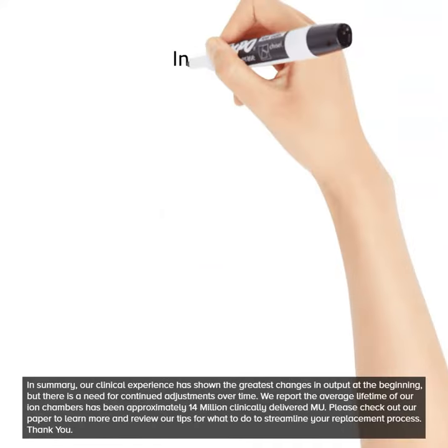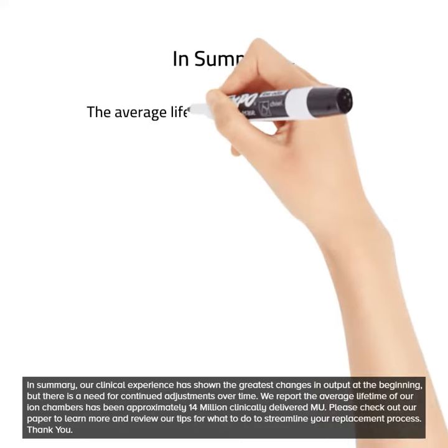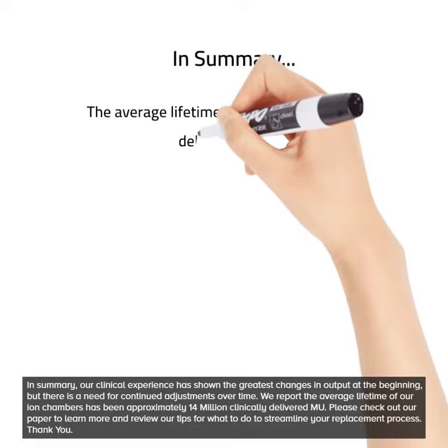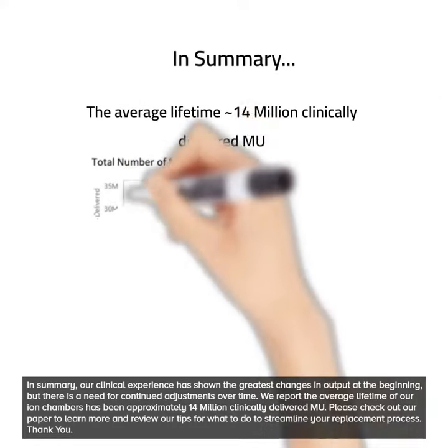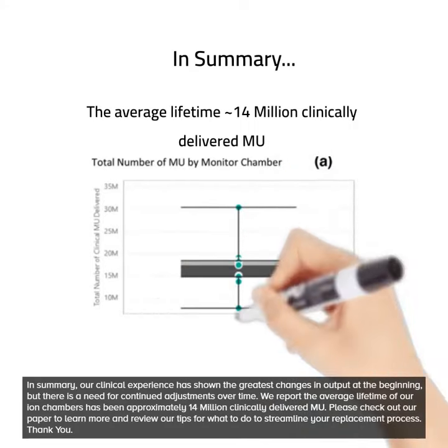In summary, our clinical experience has shown the greatest change in output at the beginning, but there is a need for continued adjustments over time. We report the average lifetime of our ion chambers has been approximately 14 million clinically delivered MU.